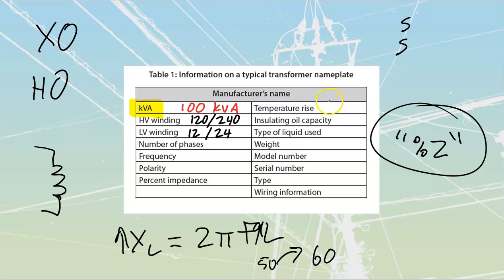Temperature rise is going to talk about how hot this thing is able to get. They will get warm. We don't want to place them any place super hot. Like, some people mount them up high on a wall. If you mount them high on a wall in a boiler room, you're going to cook that transformer, because the temperature rise talks about the maximum temperature above 40 to which the insulation may be continuously subjected. Just watch to make sure that you don't exceed that.